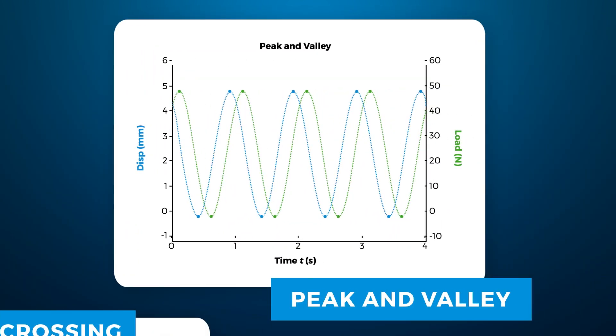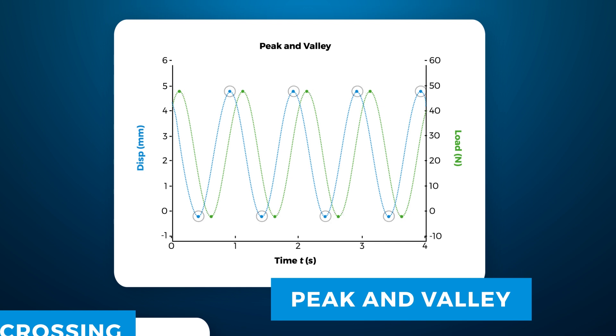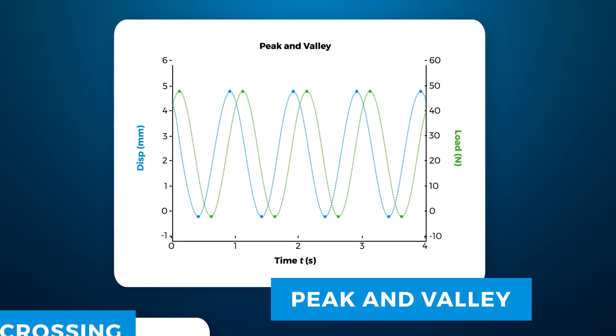Peak and valley data is another useful type of data collection, in which we collect just the maximum and minimums of each cycle for every cycle, or with set intervals between data points.